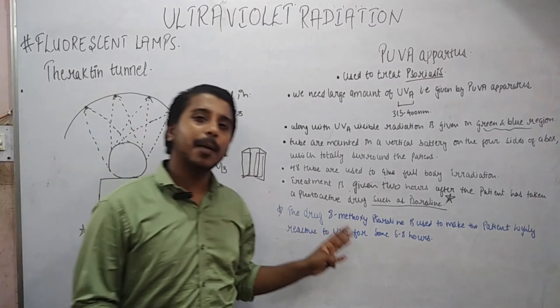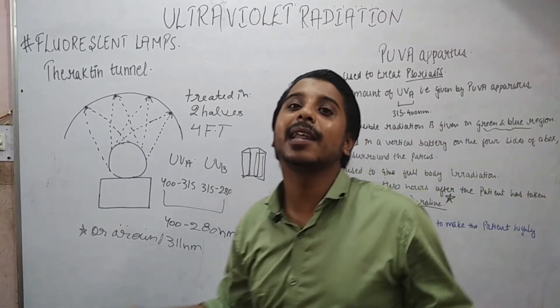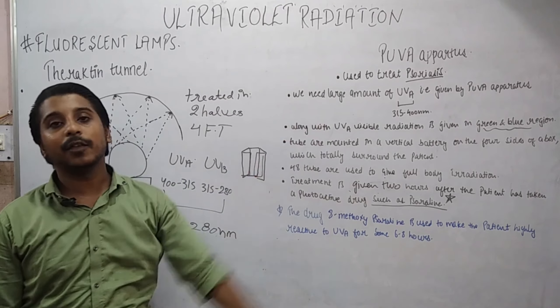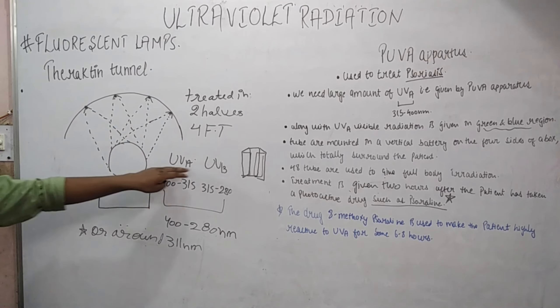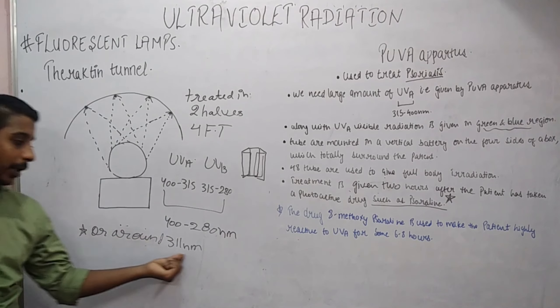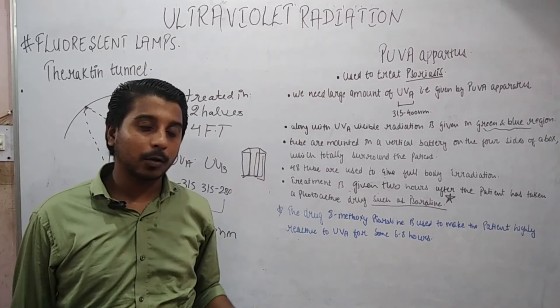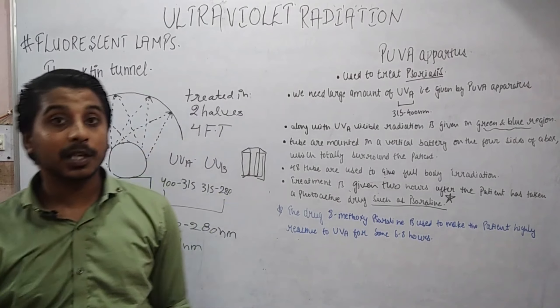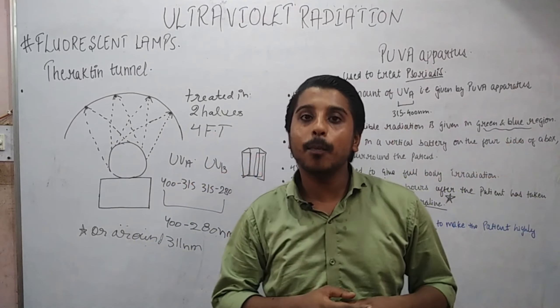So this is about the PUVA apparatus. These two are very easy — you just need to understand the previous part about the fluorescent tube; these two are simply the arrangement of tubes. The Theraktin tunnel is a semi-cylindrical frame with 4 tubes and reflectors, giving UV output of 400 to 280 nanometers, or only 311 nanometers. The PUVA apparatus requires a psoralen drug taken 2 hours before treatment to make the patient more reactive toward UVA for 6 to 8 hours, and its therapeutic effect is to treat psoriasis.